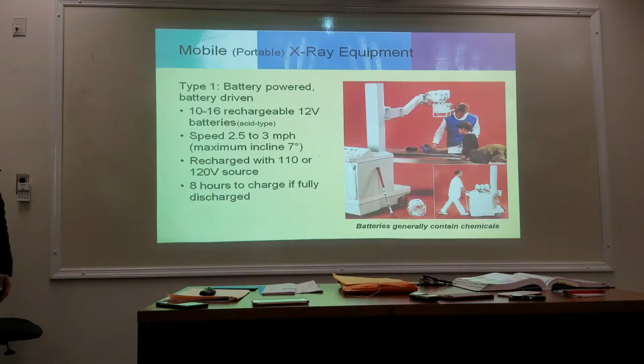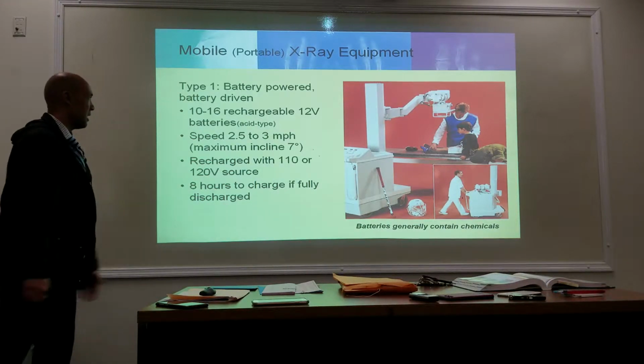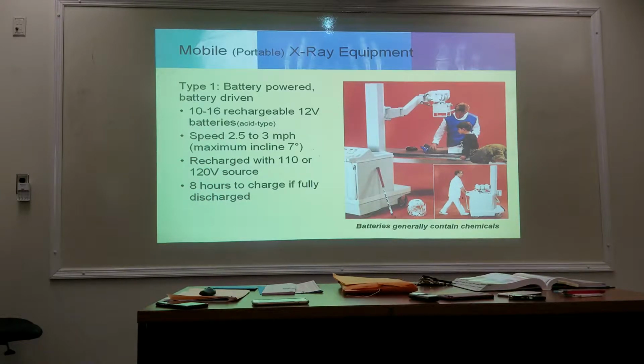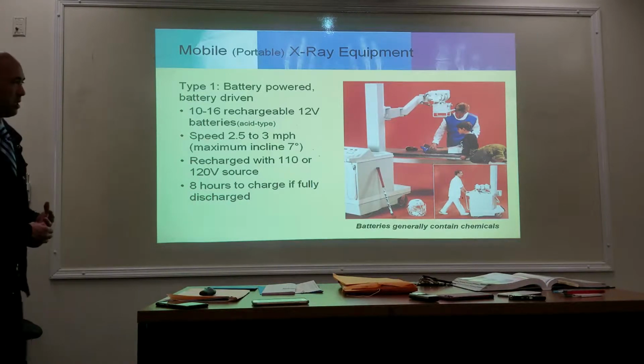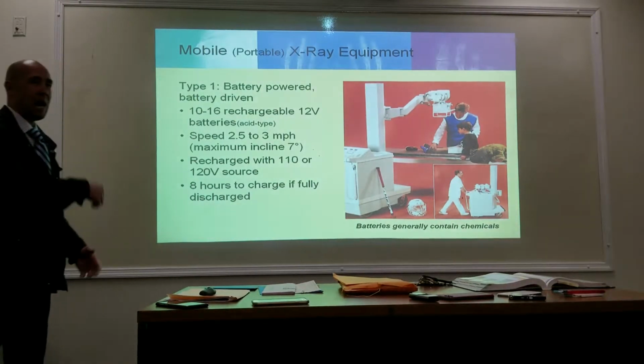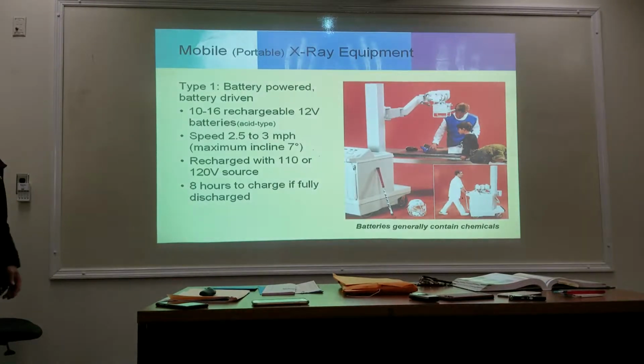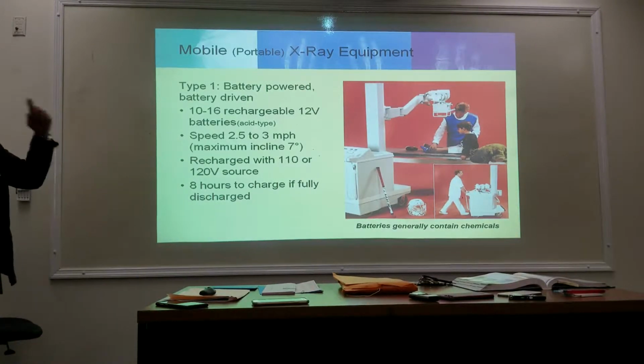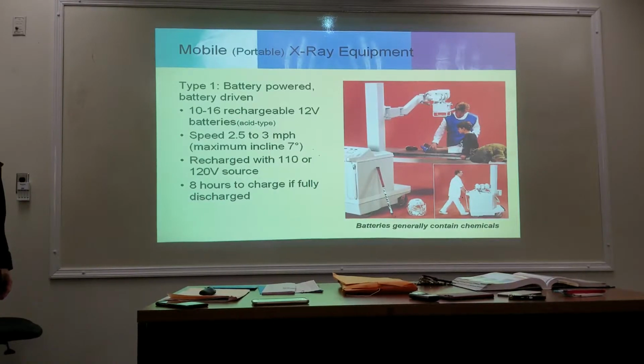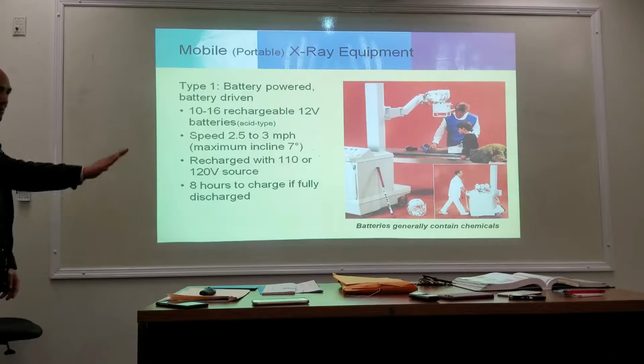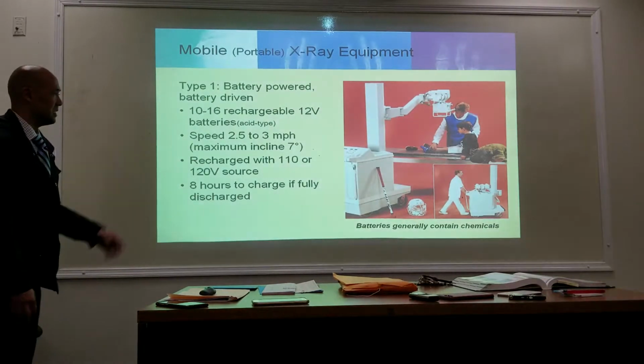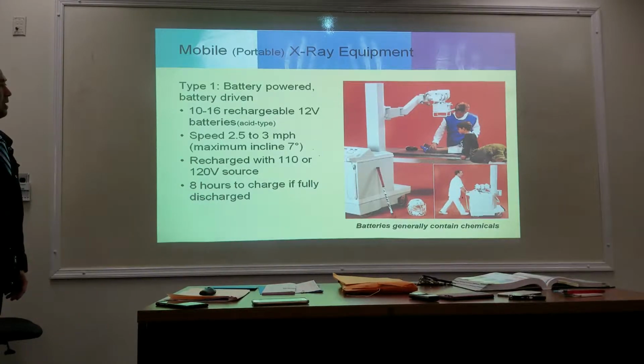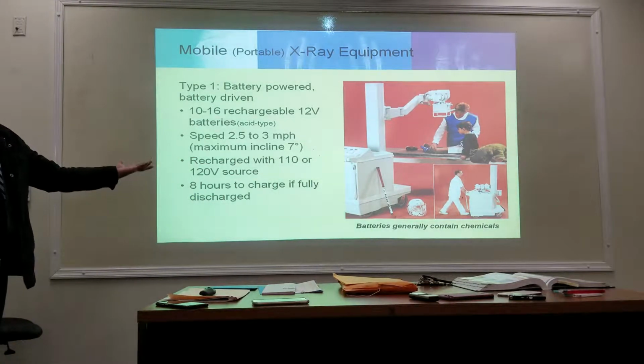Yeah. So type 1 is battery powered. They're technically acid type batteries, usually about 12 of them in connection. So 10 to 16 rechargeable batteries. Okay, batteries generally contain chemicals. They're not as strong, they're not as accurate in the power output as the capacitor type. Again, limited in power. Also, speed goes 2.5 to 3 miles per hour. The maximum incline, if you're going up a grade in the hallway, you can't go more than 7 degrees. Okay. I wasn't going to lecture about this, but it's in your book, so there it is.